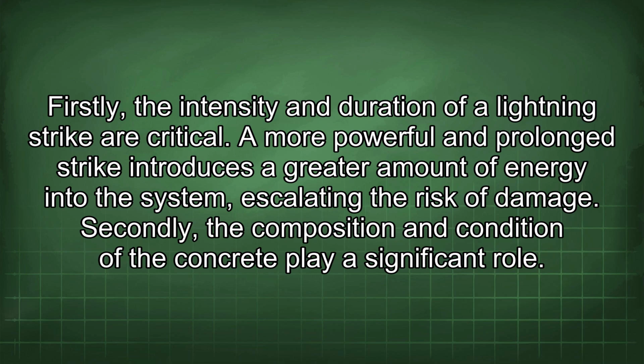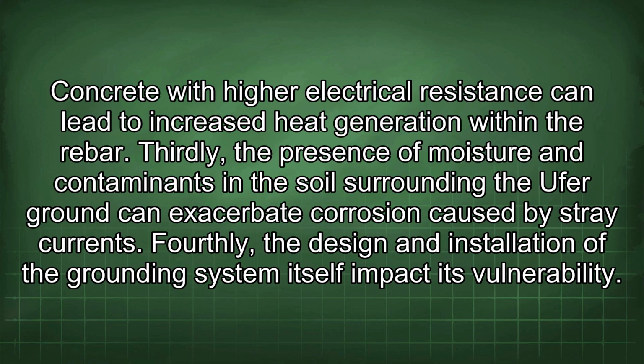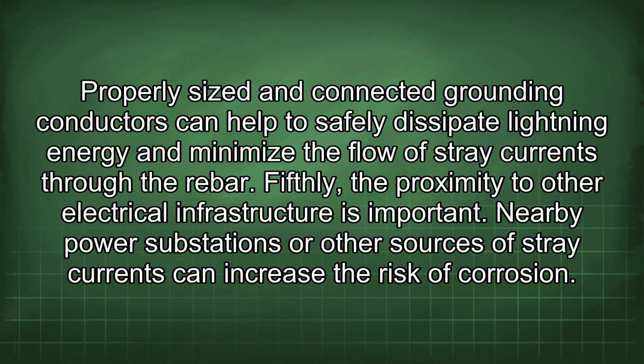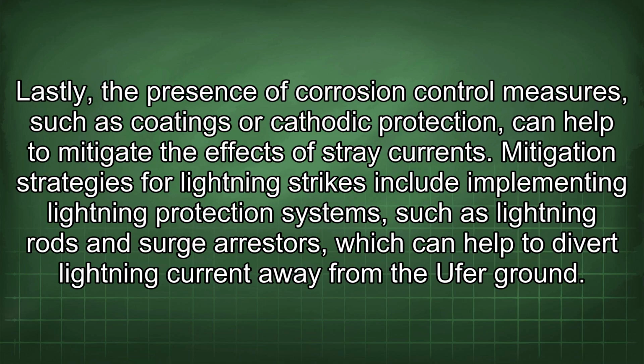Secondly, the composition and condition of the concrete play a significant role. Concrete with higher electrical resistance can lead to increased heat generation within the rebar. Thirdly, the presence of moisture and contaminants in the soil surrounding the Ufer ground can exacerbate corrosion caused by stray currents. Fourthly, the design and installation of the grounding system itself impact its vulnerability. Properly sized and connected grounding conductors can help to safely dissipate lightning energy and minimize the flow of stray currents through the rebar. Fifthly, the proximity to other electrical infrastructure is important. Nearby power substations or other sources of stray currents can increase the risk of corrosion. Lastly, the presence of corrosion control measures, such as coatings or cathodic protection, can help to mitigate the effects of stray currents.